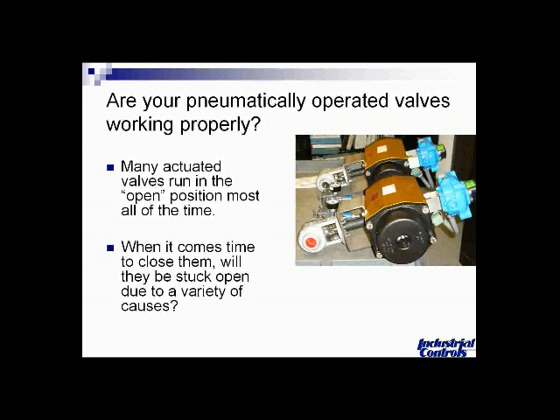causes? I mentioned earlier there's a thing called stiction that happens, especially in rotary valves, in the ball valves, when they get into that full open position and they've been sitting there for months, they tend to get in the locked position, and so the breakaway torque increases quite a bit at that point. So there's a chance where a critical valve or some critical valves could actually be left in an open position, and when you need them to close, they just don't make it.